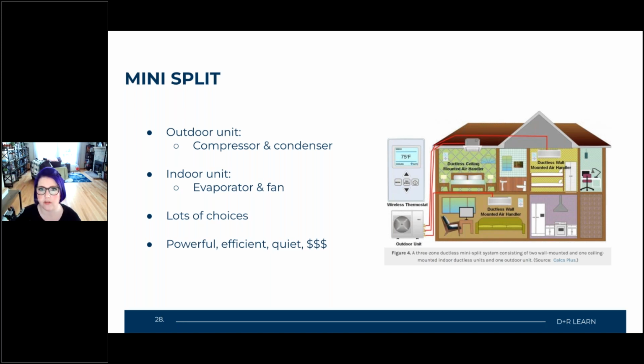Heat pumps use the vapor compression cycle, and the efficiency of that cycle depends on a lot of things. One consideration is your refrigerant, because as a chemical that is evaporating and condensing, different refrigerants have a band of temperatures they operate most effectively at, and beyond that band they aren't very effective.